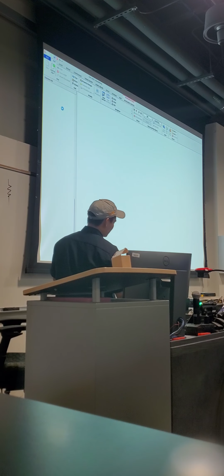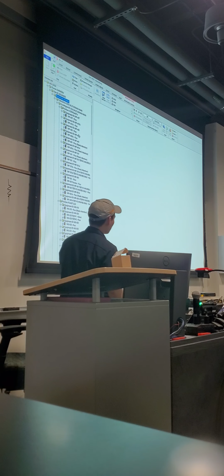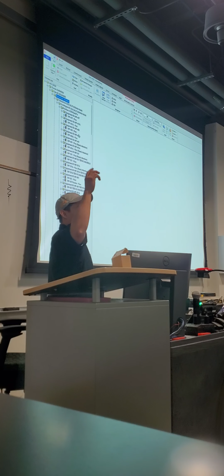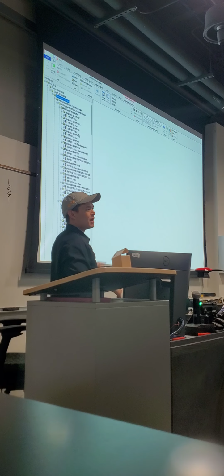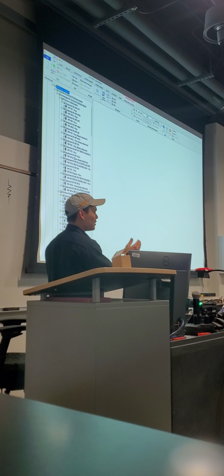So this will take a while because there's a lot of work, man. Job security, right? What we're seeing here is sorted by substation, sorted by equipment ID. All of these here are a bunch of motors. I picked this one because this was a case study I talked about. You remember we saw in the news that one refinery down by LAX that caught on fire. Well, these were all the motors that we tested, as simple as running a Megger test, PI. We PI'd all those motors, so a lot of billable time, right?